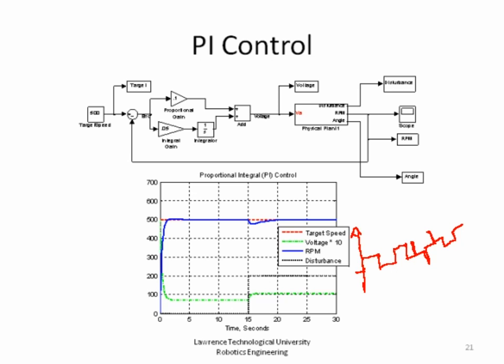I've drawn it as straight up, but really from sample to sample, you get a very high slope. And that tends to drive that derivative control to do a drastic change when there was no need. It's just a little noise, either A to D noise or just noise you've picked up from electrical noise and things like that. So typically, to use a derivative control, you want to add some filtering to kind of smooth it out, which then kind of undoes the derivative effect, but with a little work, you can make it work. And what I'll do is, down in the description, I'll put in a little sample pseudocode of how you might implement all this.